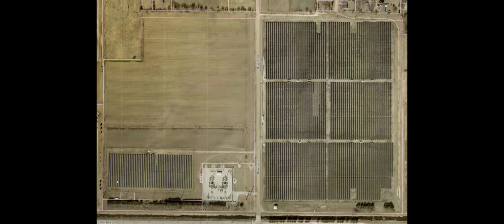Another caveat to this, which we are working on right now, is we have an interruptible load locating on the north side of that substation that will be between 10 and 12 megawatts. So for large parts of the day, the output of that solar will feed that farm without ever going through our transformers - without taxing the transformers for certain parts of the day, we can power that interruptible facility. We also own the land to the north, which has potential for, I believe, 7 megawatts of more solar at a later date.